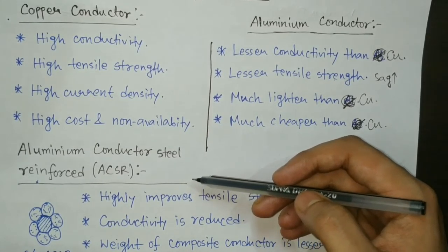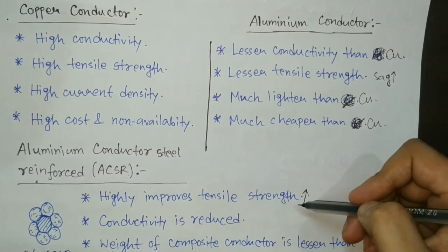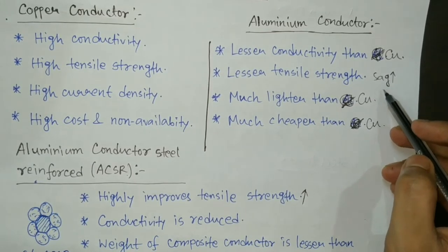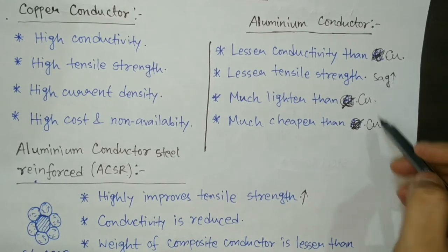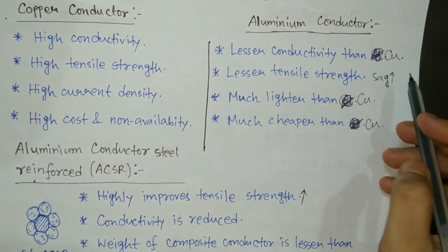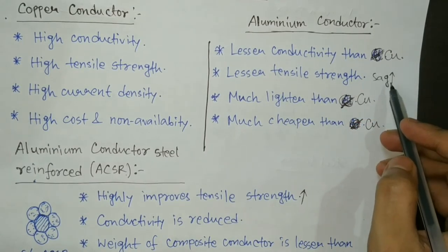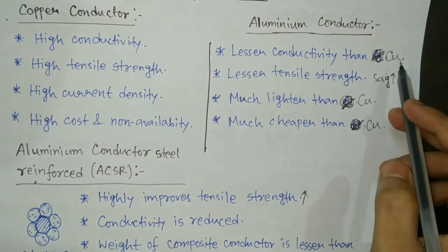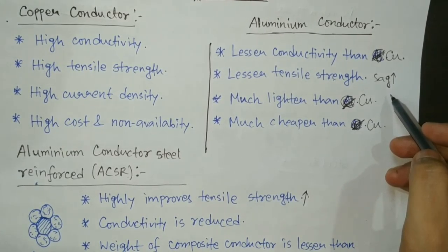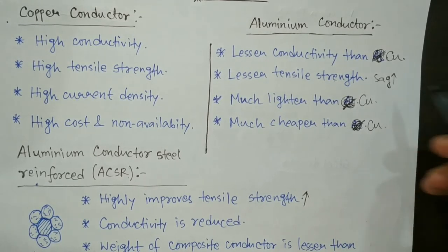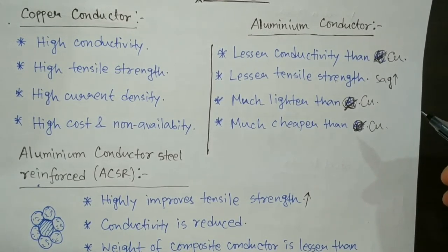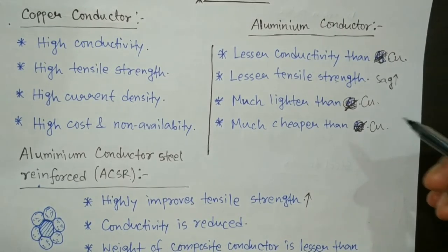ACSR conductors are widely used for long transmission lines. Due to the improvement in tensile strength, the problem of sag is gone. As a result, the height of the tower can be reduced, because previously — with plain aluminium conductor and high sag — the tower needed to be very high to maintain ground clearance. With reduced sag, the tower height doesn't need to be very high, which also reduces the cost of the tower.